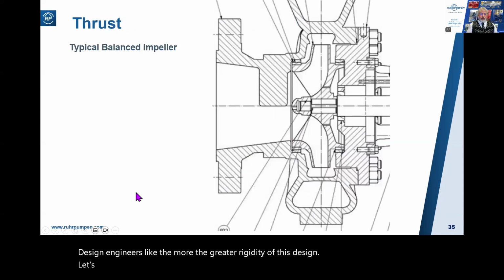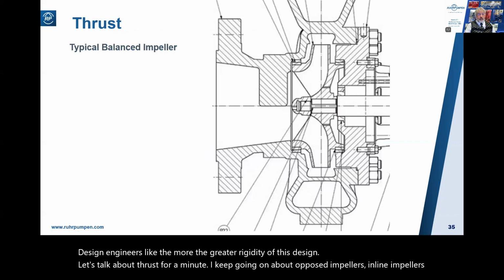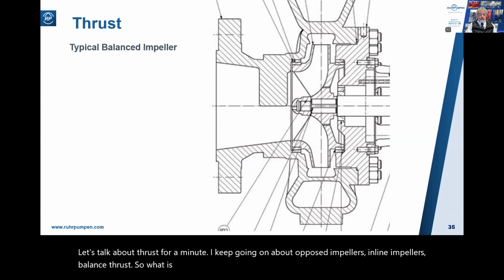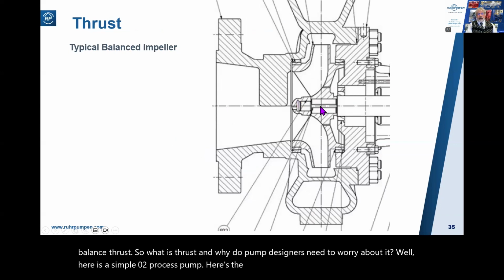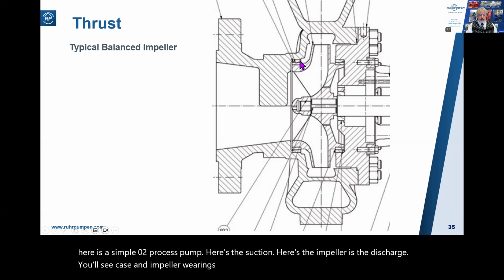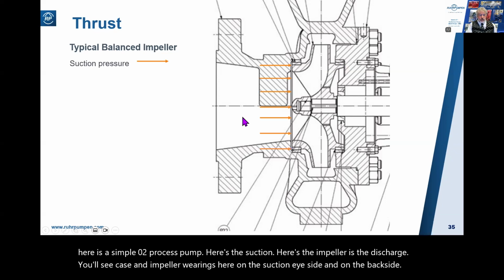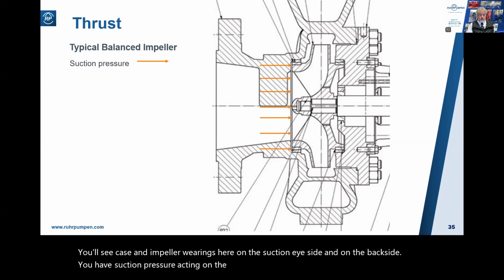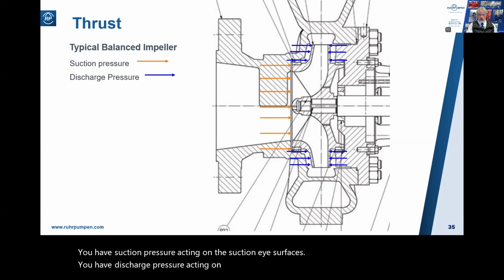Let's talk about thrust for a minute. I keep going on about opposed impellers, inline impellers, balanced thrust. So what is thrust, and why do pump designers need to worry about it? Well, here is a simple OH2 process pump. Here's the suction, here's the impeller, here's the discharge. You'll see case and impeller wear rings here on the suction eye side and on the back side. You have suction pressure acting on the suction eye surfaces. You have discharge pressure acting on these areas, shown in blue here.